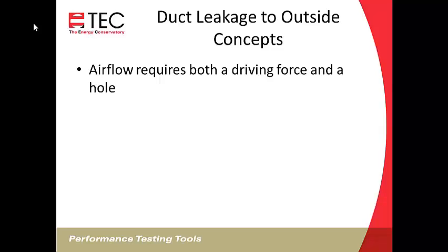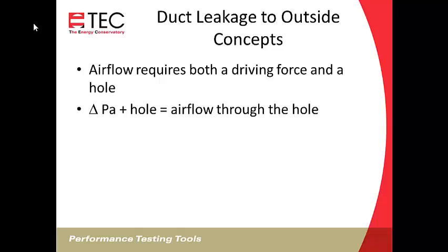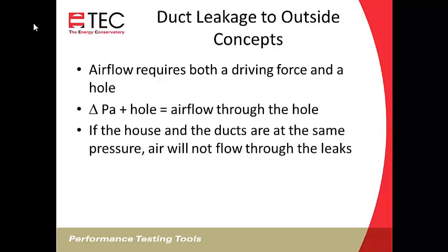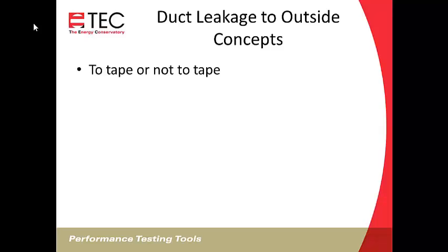Airflow requires both a driving force and a hole. In the case of duct leakage testing, the driving force is the difference in pressure. So we need both the difference in pressure and a hole in order to get airflow across that hole. If the house and the ducts are at the same pressure, then air will not flow through those leaks. So that's the basic concept to keep in mind when we're doing duct leakage to outside testing.